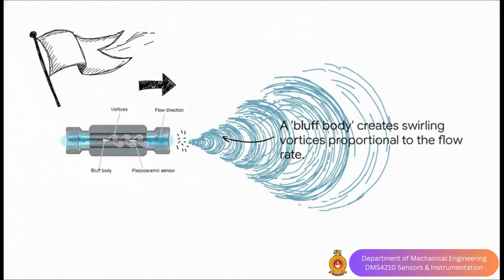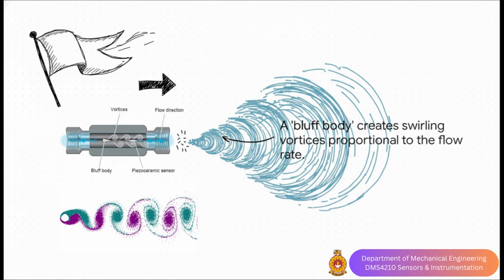See that little wedge-shaped object inside? That's called a bluff body. As fluid rushes past it, it creates this perfectly stable, repeating pattern of swirling eddies, or vortices. It's just like a flag flapping in the wind: the faster the wind, the faster the flag flaps. Same thing here, the faster the fluid, the faster the vortices are created. A sensor inside just counts those vortices, and that frequency gives you a super precise flow rate.